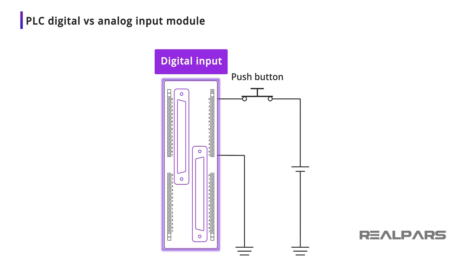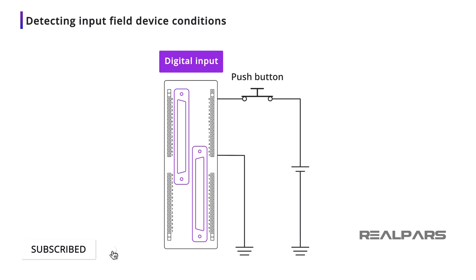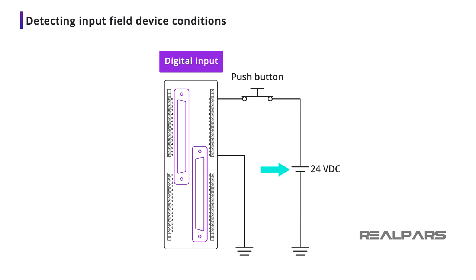As we said earlier, a digital input module will detect one of the two possible conditions of an input device — open or closed. So, the question is, how does the input module know if the input device is open or closed? All we need to do is construct a closed circuit containing the input device, the PLC input module, and a 24 volt DC power supply.